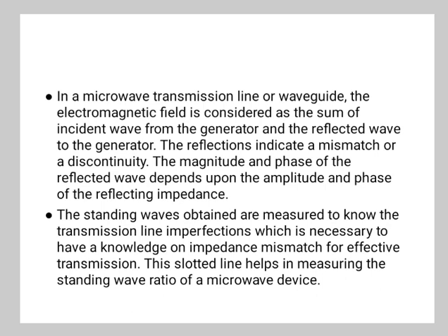It is important that the probe should be very thin compared to the wavelength, and the depth should be small enough to avoid any field distortion. So the slotted line carriage with a tunable probe detector can also be used to measure wavelength, standing wave pattern, VSWR, reflection coefficient, impedance and return loss.